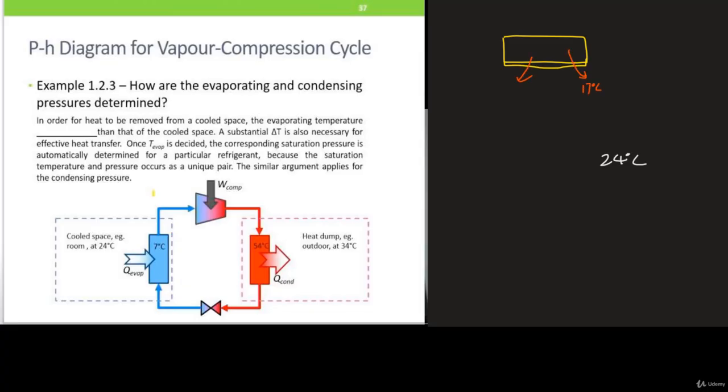A common misunderstanding is that when you change the set point on your remote control from 24 to 23, it is not changing the set point of the supply air, the air that is coming out. It is changing the set point of the air that is returning to your air conditioning system.